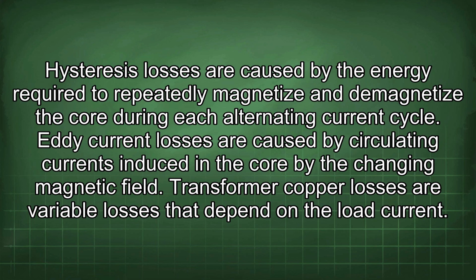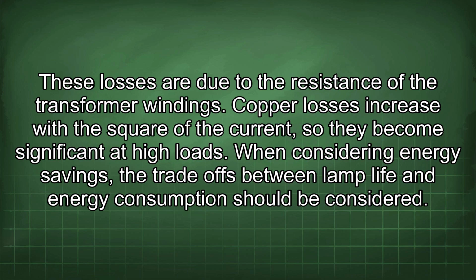Transformer copper losses are variable losses that depend on the load current. These losses are due to the resistance of the transformer windings. Copper losses increase with the square of the current, so they become significant at high loads.